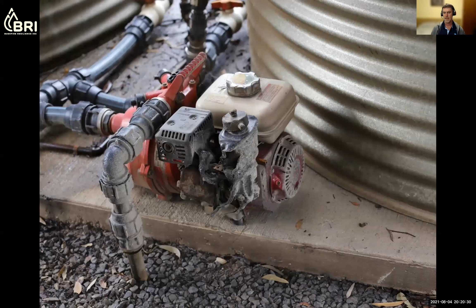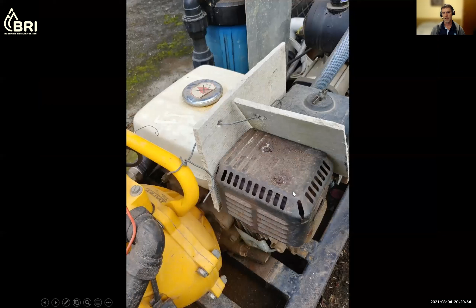Here's an example of one of those pumping systems that ingested embers during a fire, and it suffered a flaming failure of the inlet air filter that shut the pump down, and that won't be functioning ever again.